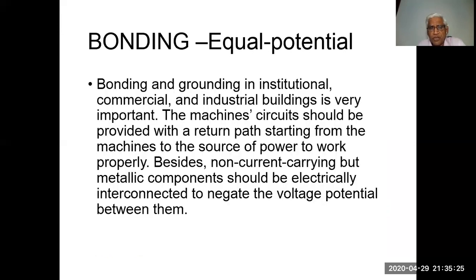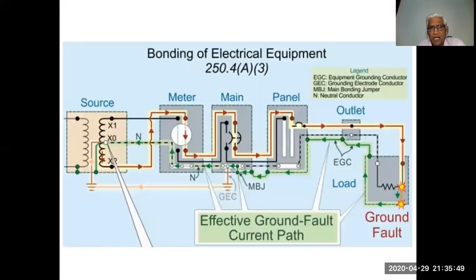Bonding and equipotential. Bonding and grounding in institutional, commercial, and industrial buildings is very important. The machine circuits should be provided with a return path, starting from the machine to the source of power, to work properly. Besides, non-current carrying but metallic components should be electrically interconnected to negate the voltage potential between them. Now, bonding of electrical equipment is given in Article 250.4 of NEC.